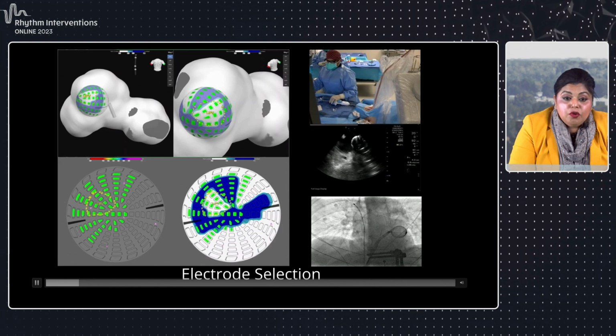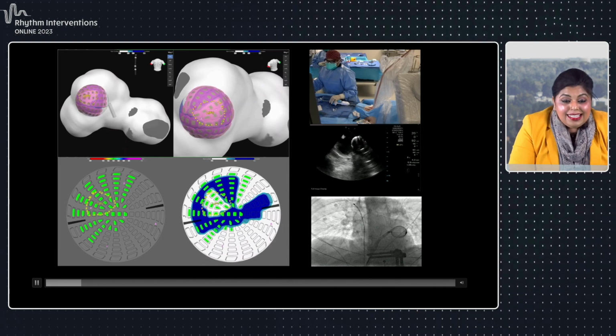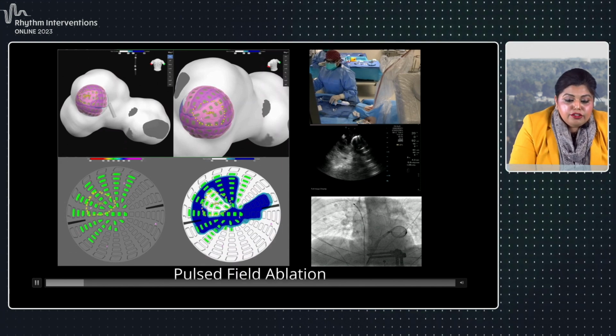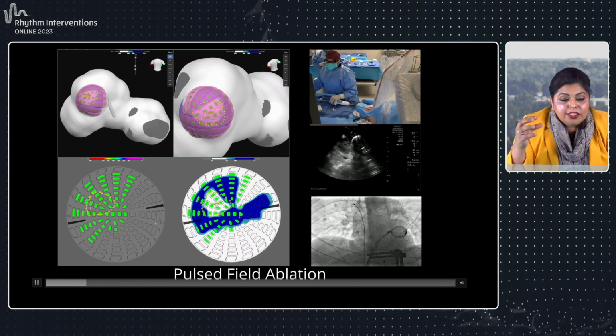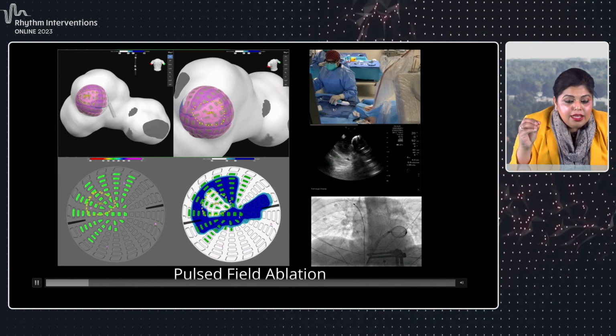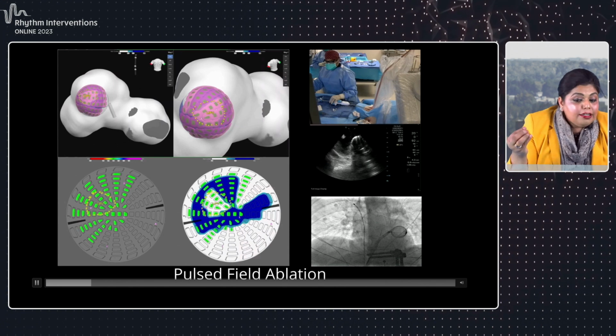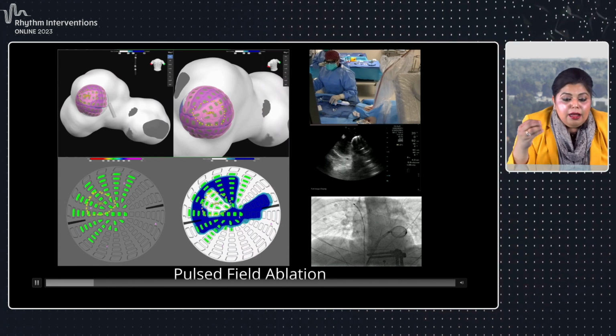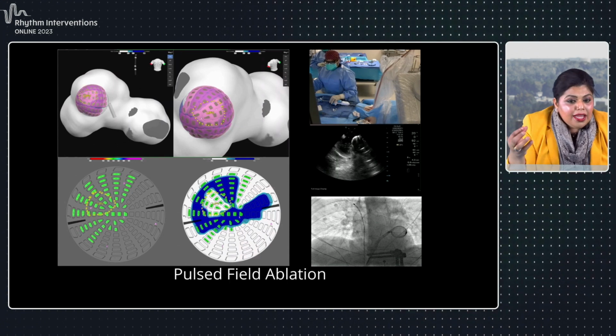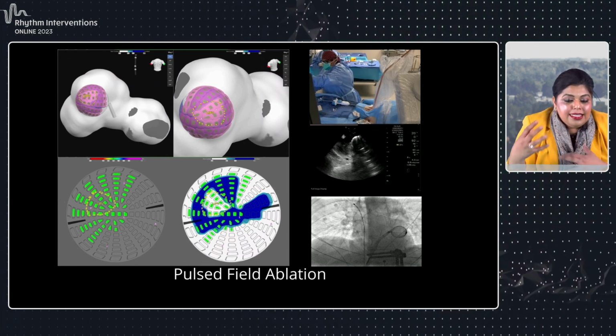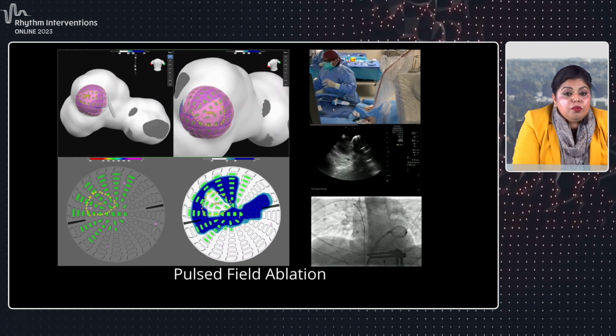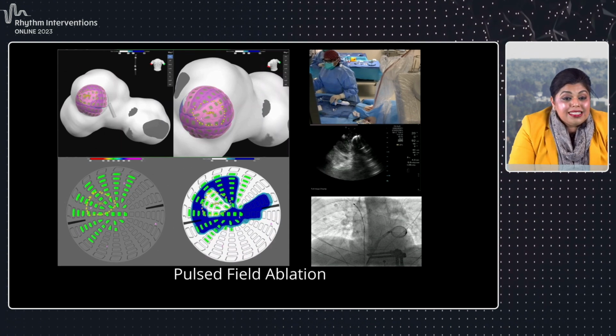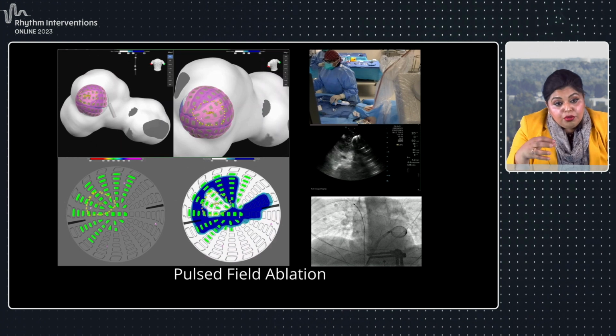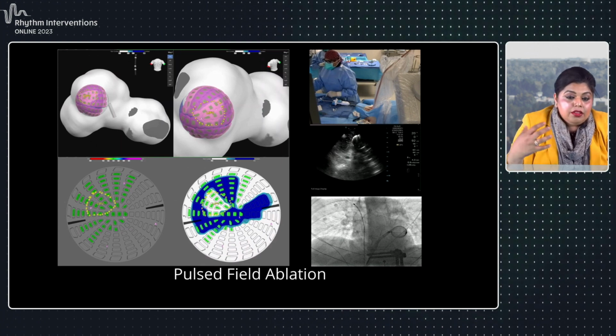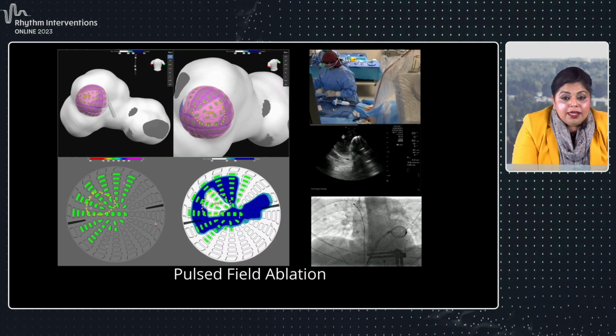On the left, you can see the voltage. I pause and I select my electrodes. The way you select the electrodes, you can select the electrodes that have contact to tissue. It's a very precise selection. Then you add additional electrodes to make a valid bipolar ablation path. It's okay to add electrodes that are not in contact with the tissue to create that nice bipolar ablation path. So here we are selecting the electrodes. You can see it on the globe, you can see it on the 3D map, and you can see it on the array that is being shown in the bottom as well.